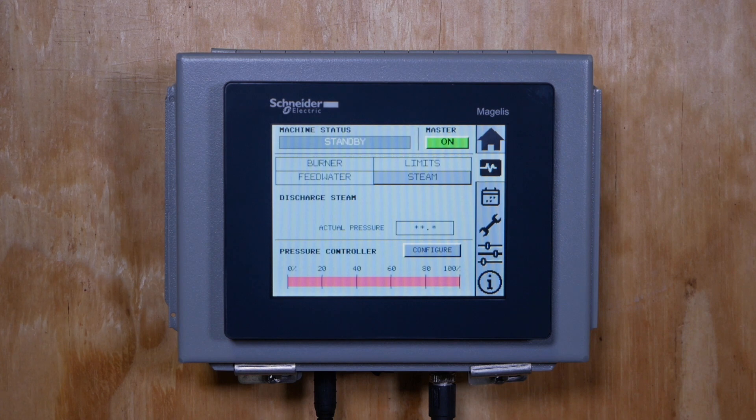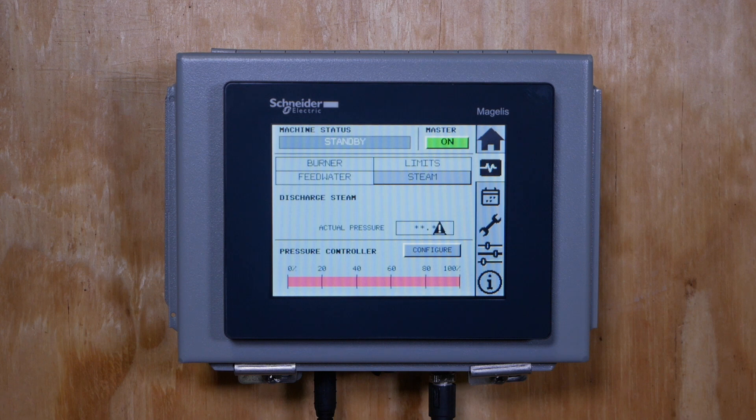The steam page shows the steam output setpoint and actual pressure. The pressure controller graph shows the steam demand. As the steam demand drops, the burner will switch to low fire mode and eventually turn off.